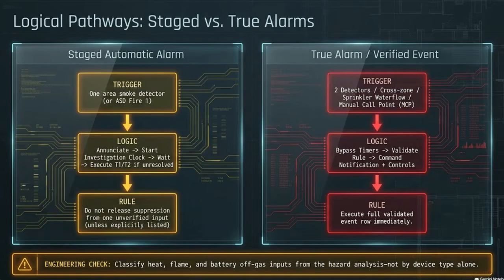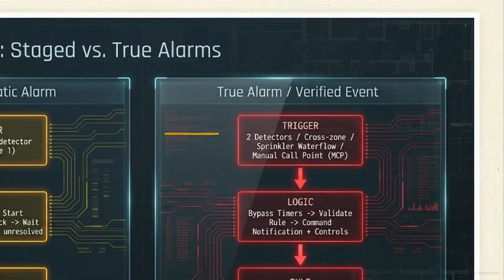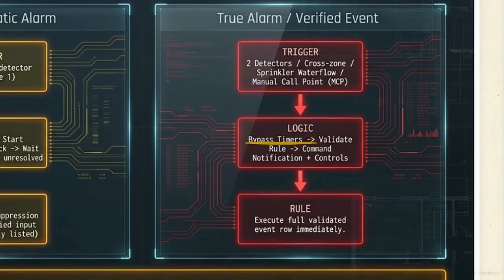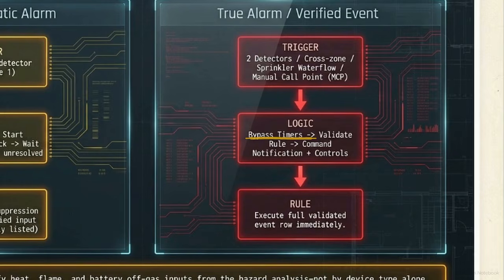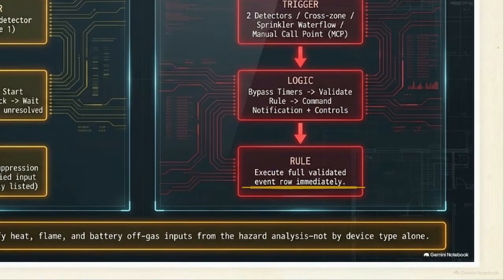This logic flowchart contrasts that yellow staged pathway with the red true alarm pathway. A true alarm relies on high-confidence inputs, like 2 detectors tripping in a cross-zone setup or a manual call point activation. When the panel receives a verified confirming event, it instantly bypasses all optional stage timers. It validates the rule, commands the notification, and executes the full event row immediately.